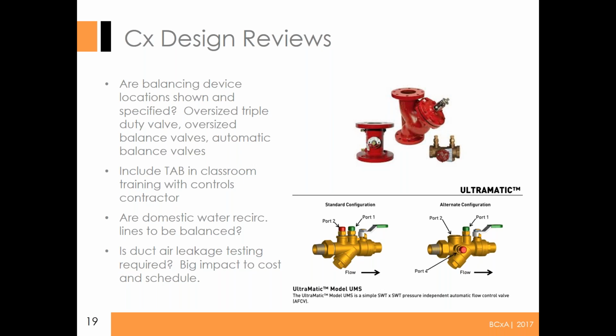So look for locations. I mentioned oversized triple duty valves. Anything that's line sized that needs to measure something is oversized if it's the same size. Everybody knows that for control valves. Unfortunately, engineers often size the balancing valves too, when they should just put the GPM on and let it be sized smaller. If it's too big, it'll be cracked so low it upsets the whole flow.